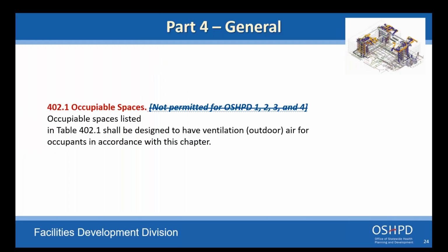Now, 402.1, what we're doing there is we're taking out that banner that says not permitted for OSHPD. Just so you know, currently with the current express terms that are open for public comment, we're also doing the same for 402.0. What we're doing here is we are moving towards having these facilities, our facilities, ventilated per 62.1, in addition to ASHRAE 170 type of requirements. And all of that needs some clarification, which I'm currently working on, but that's what we're doing here. Next slide, Caesar.